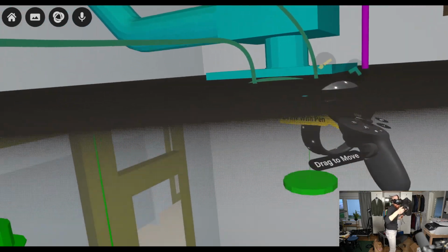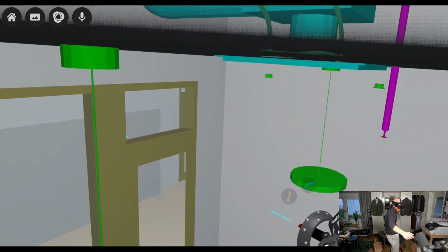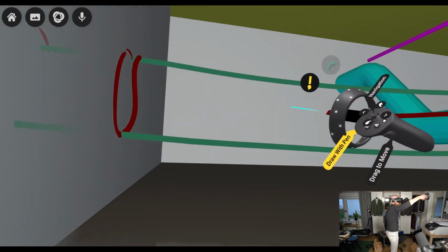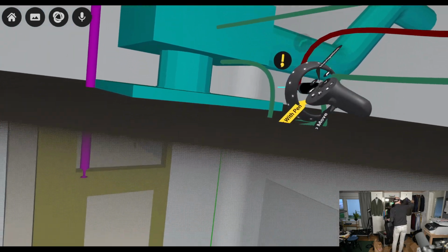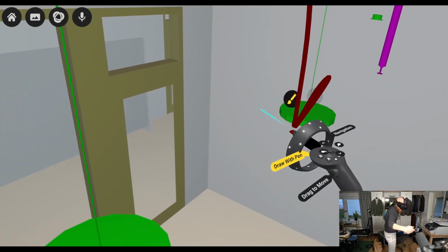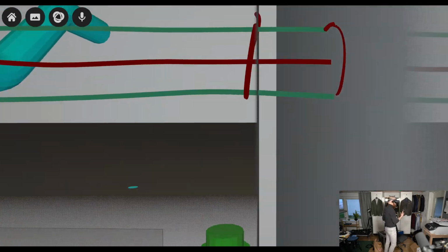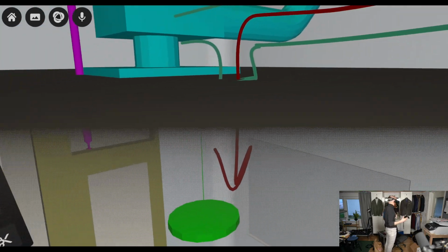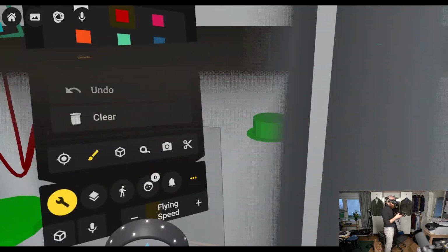And another one is channel transmission. I mean, when people are inside this room talking, the sound of the speech will enter the channel, and once it's inside the channel, it's got nowhere else to go and just keeps going, and then it will find the exit here. So you always have to consider this transmission path inside the channel. This is the same principle like you know in the old movies when they call from the bridge down to the engine room in the big ship. They call full speed ahead, then this is the same principle. And you have to do something about that.